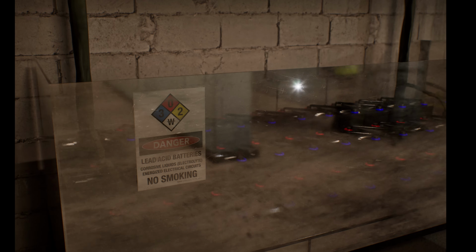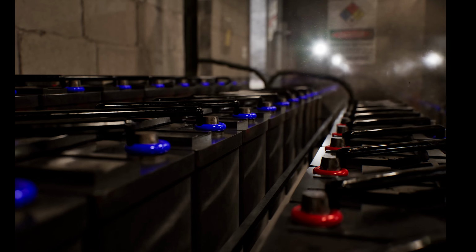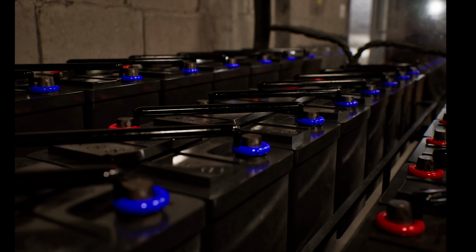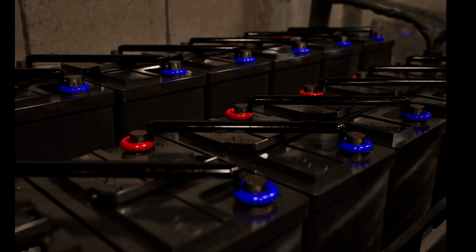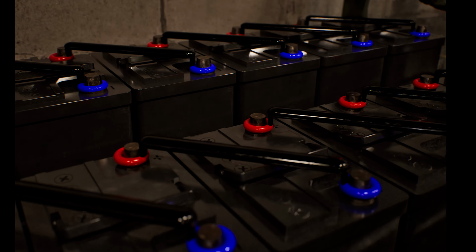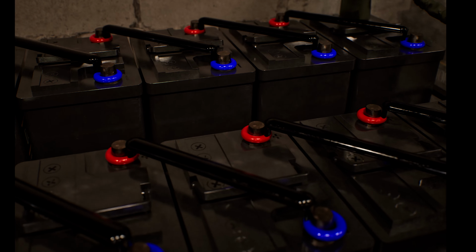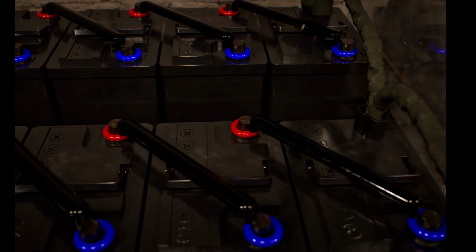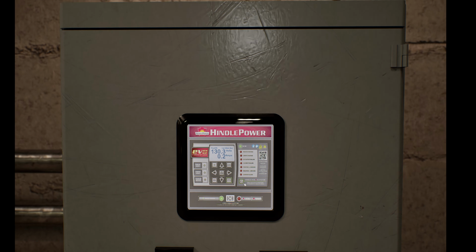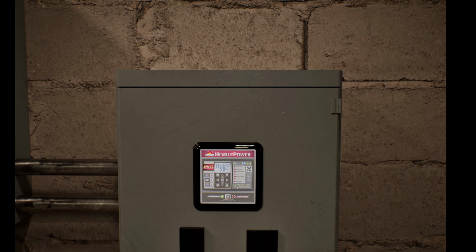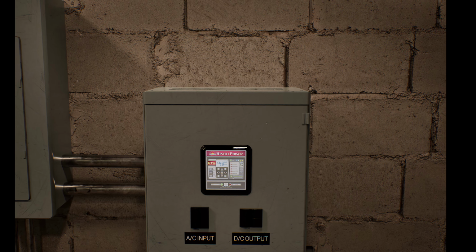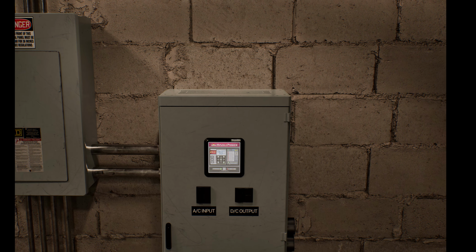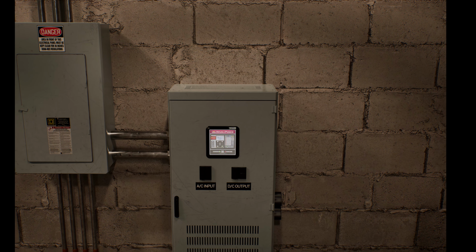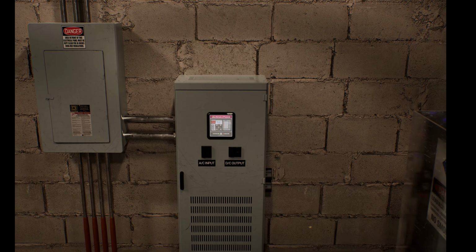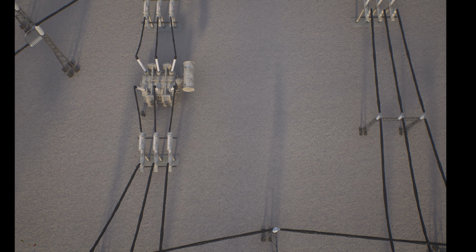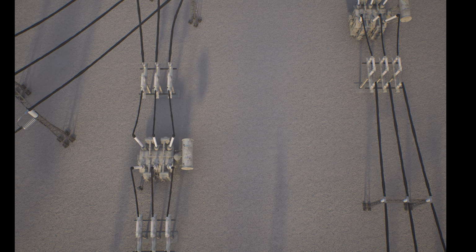Only approved and properly rated tools and test equipment may be used inside a substation. NFPA 70E requires tools and test instruments to be rated for the voltage and environment in which they are used. Inspect all tools before use. Keep work areas organized and ensure tools are positioned safely away from energized components. Conductive tools should never be used unless specifically designed and approved for the task.